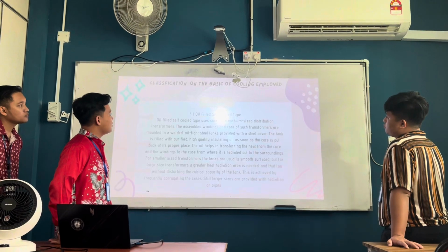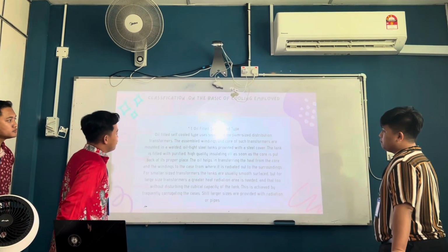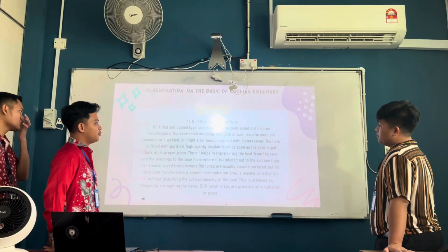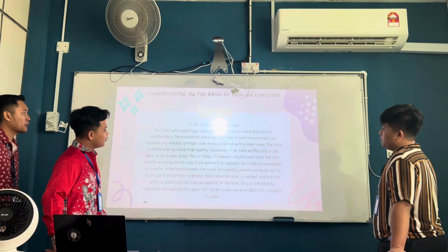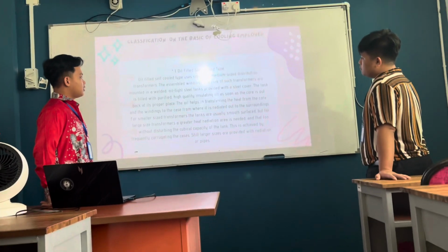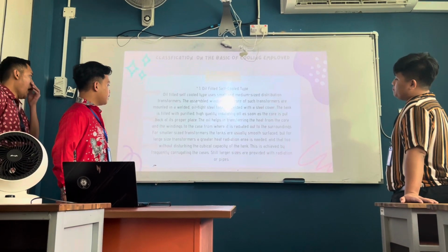Okay. This is the classification on the basis of cooling employed. The first one is oil-filled self-cooled type. Oil-filled self-cooled type is used in small and medium-sized distribution transformers. The assembled windings and core of such transformers are mounted in oil-tight steel tanks provided with a steel cover. The tank is filled with purified high-quality insulating oil.